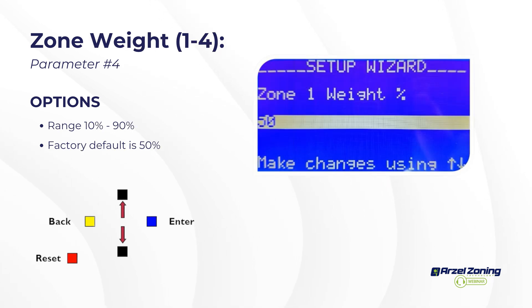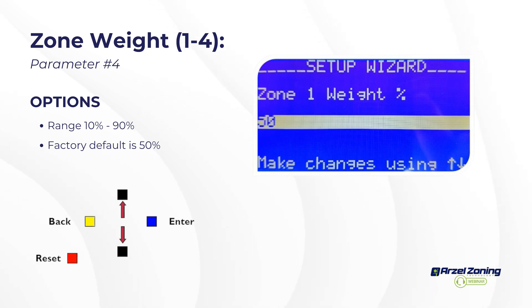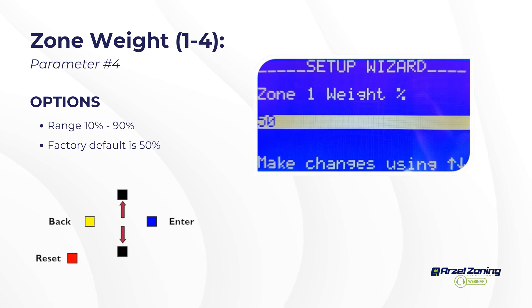For individual zone weights, use whole numbers — 50, 40, or 20. The next key setting is air handler stage threshold, factory default 50. If your zone weight equals or exceeds 50, W2/Y2 second-stage outputs are allowed. If a zone is set to 40, that's less than 50 so W2/Y2 are disabled — you need at least two zones calling to enable second-stage capacity. If two zones are set to 20, their combined 40 is still less than 50, requiring three zones.